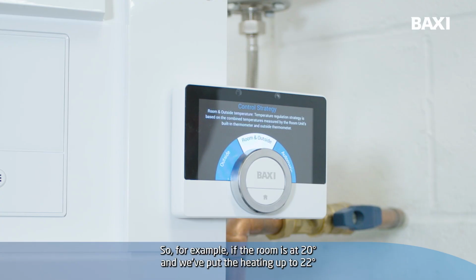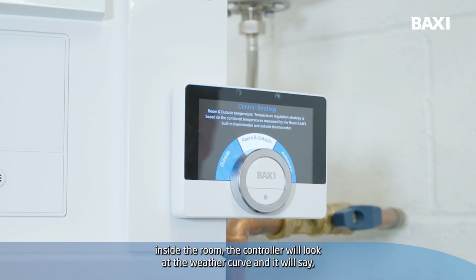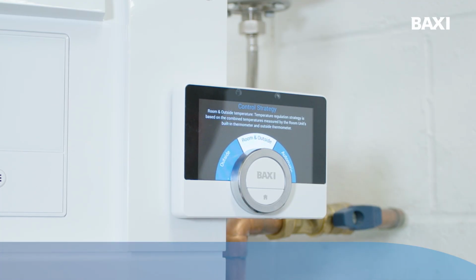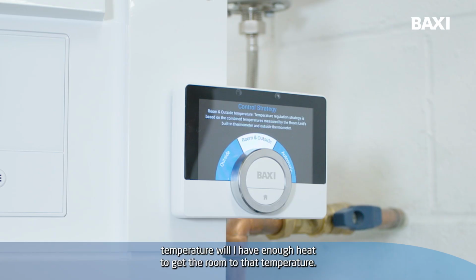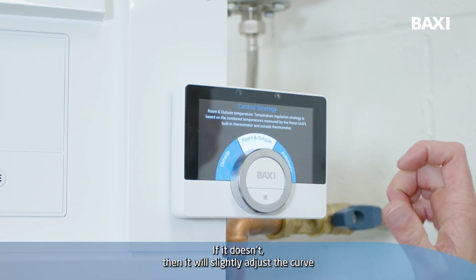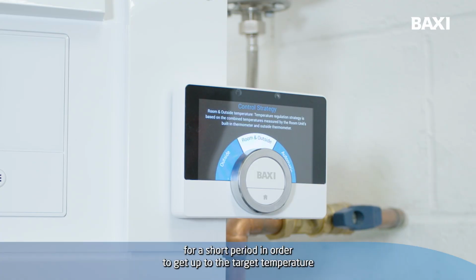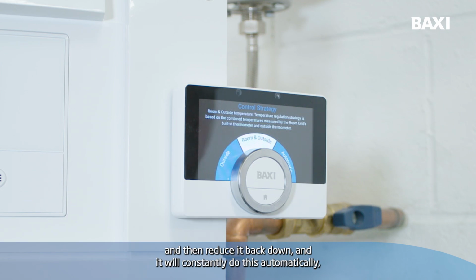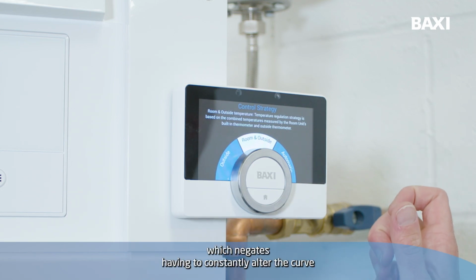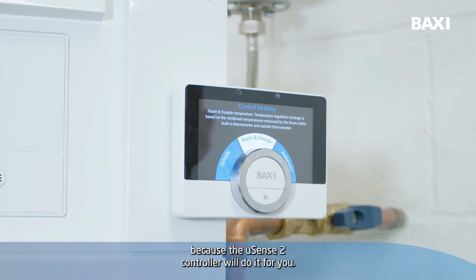So for example, if the room is at 20 degrees and we've put the heating up to 22 inside the room, the controller will look at the weather curve and it will say, at this current flow temperature, will I have enough heat to get the room to that temperature? If it doesn't, then it will slightly adjust the curve for a short period in order to get up to the target temperature and then reduce it back down. And it will constantly do this automatically, which negates having to constantly alter the curve because the uSense 2 controller will do it for you.